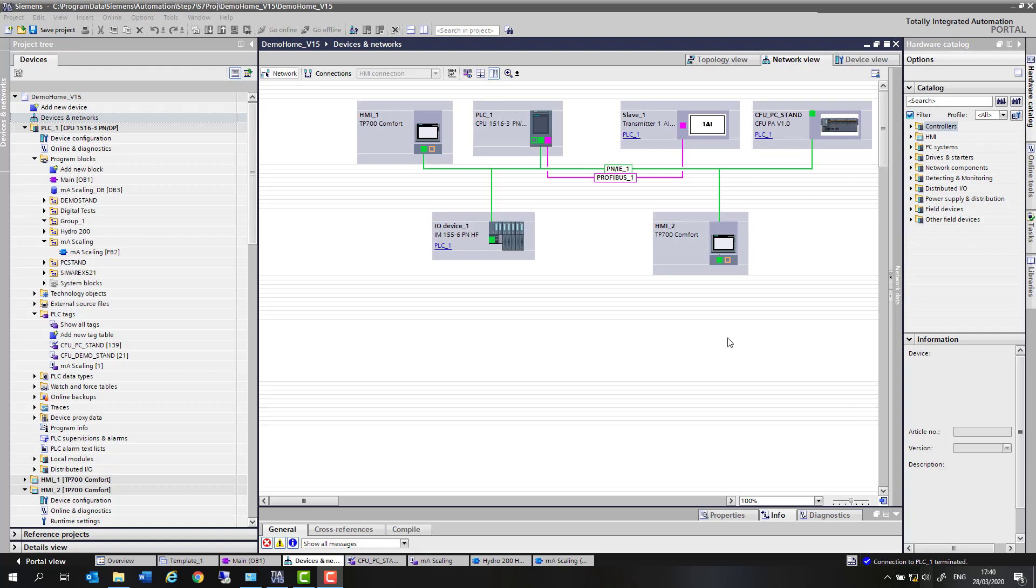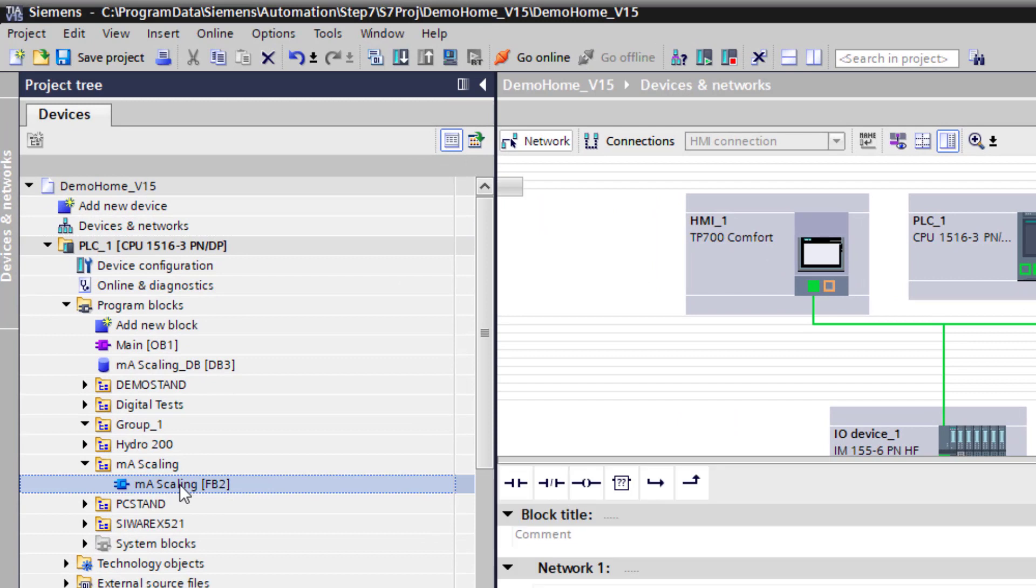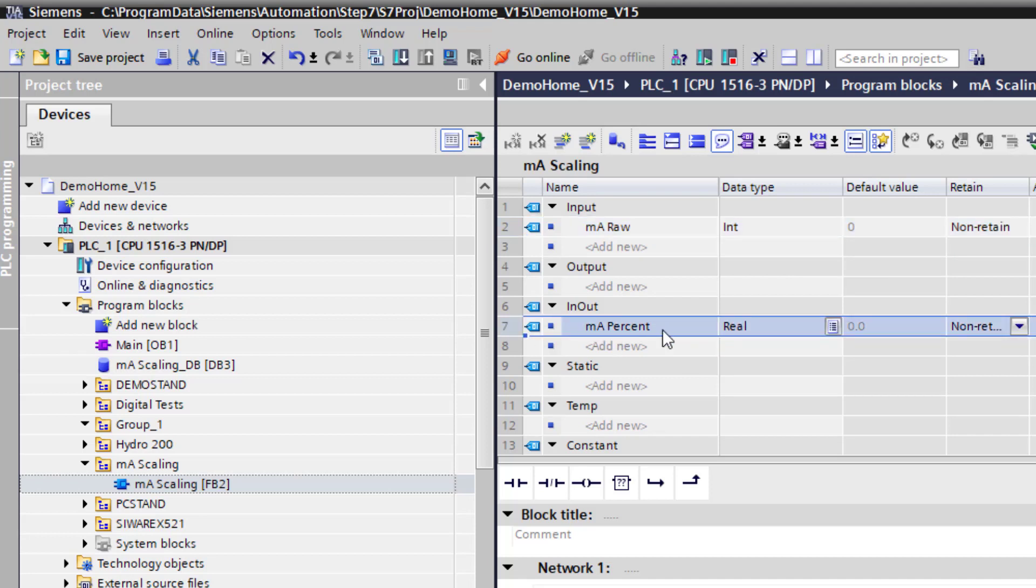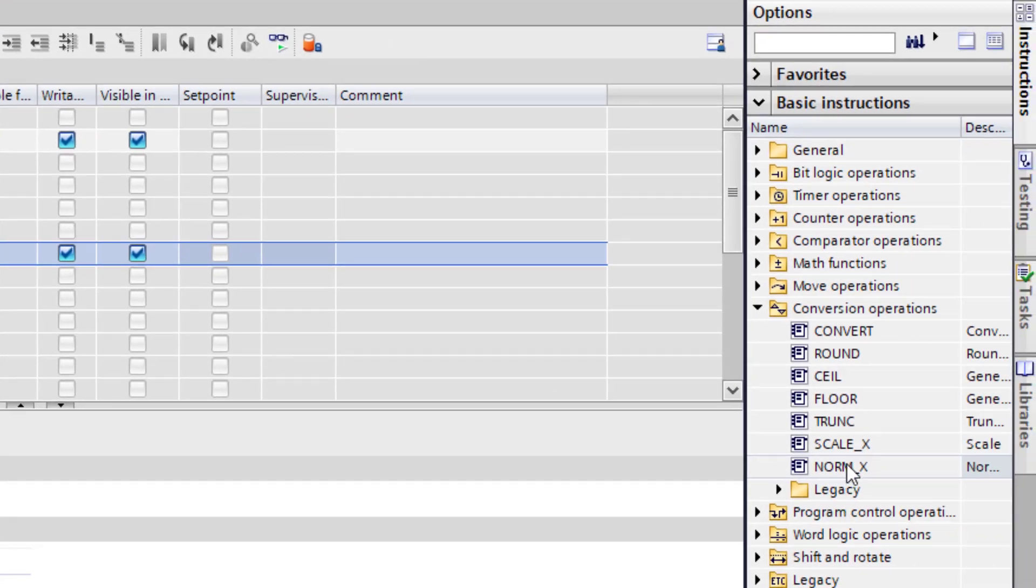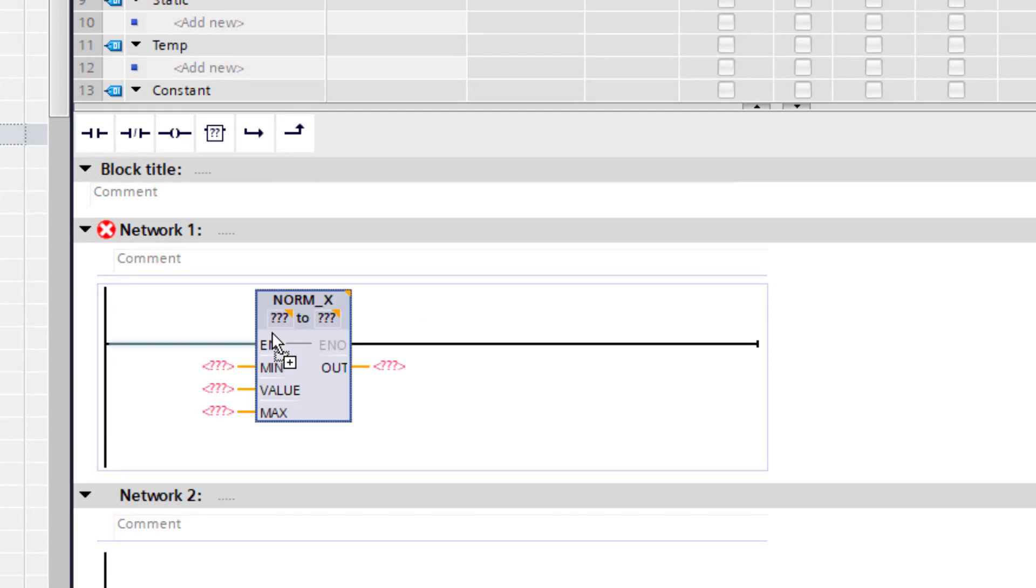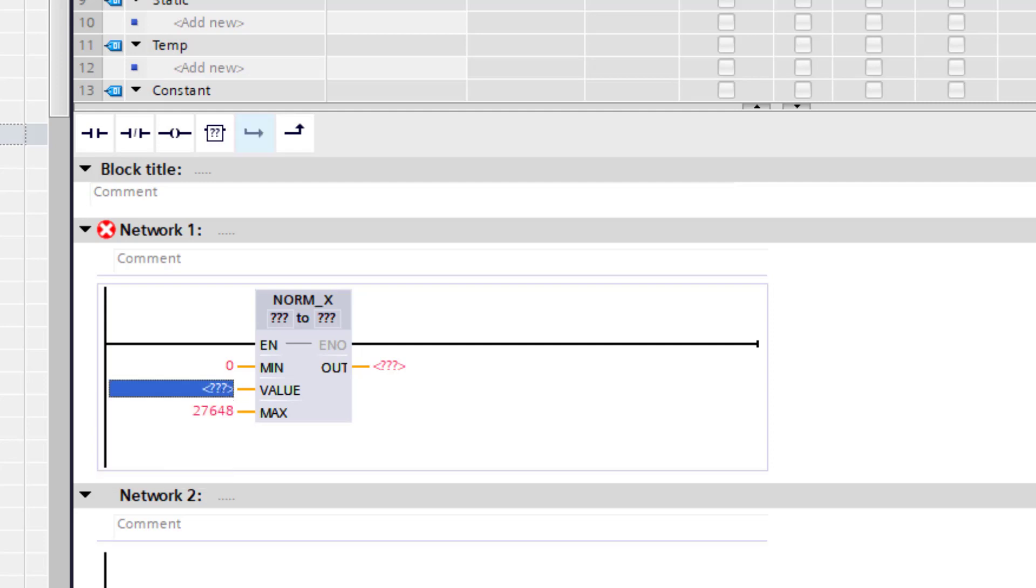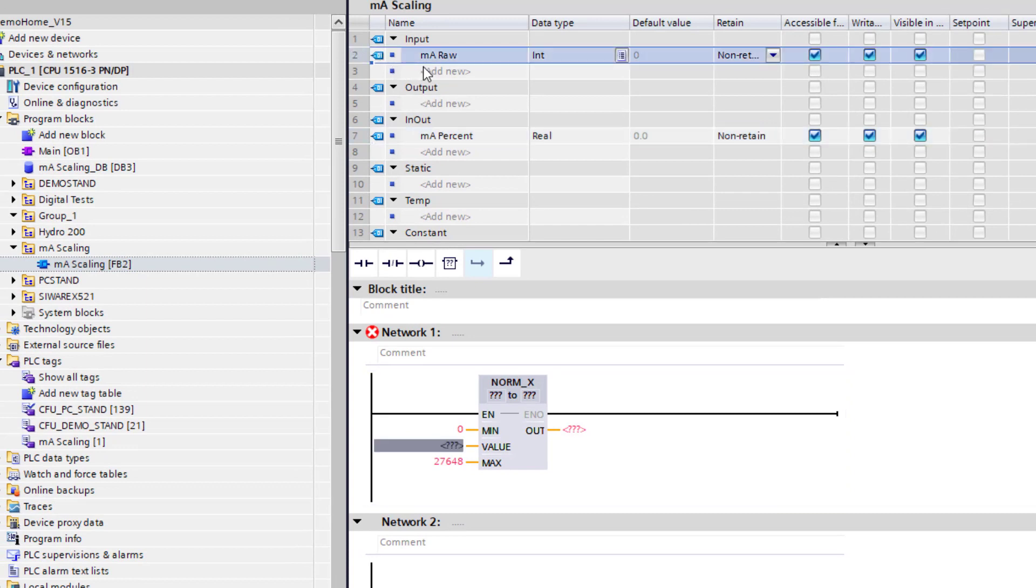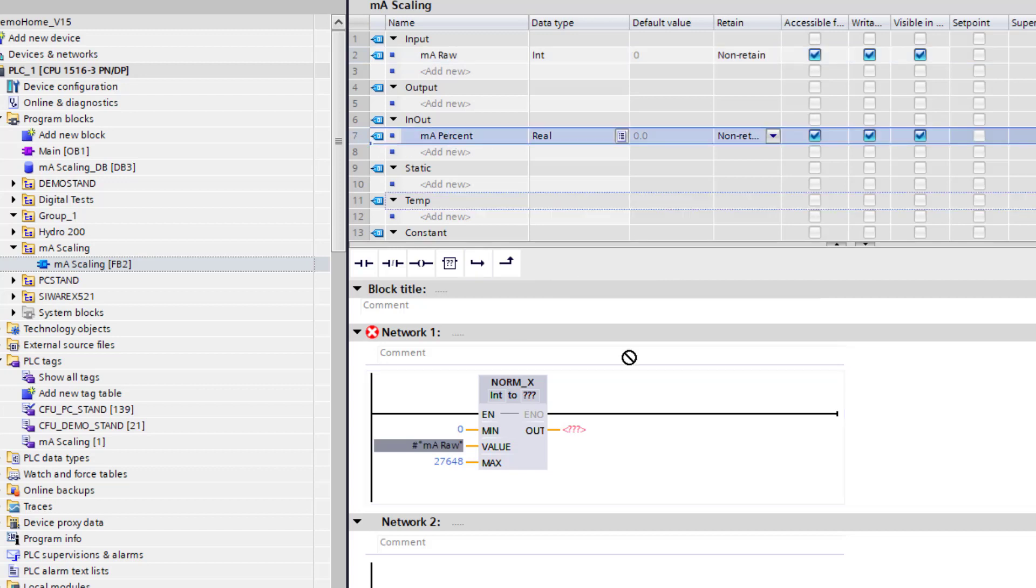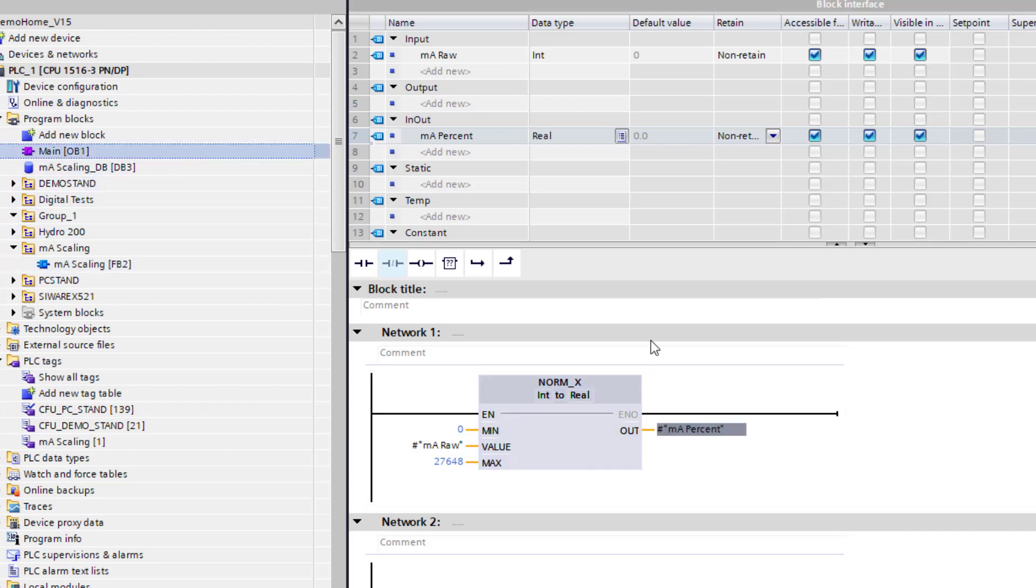So I've created a block called milliamp scaling, and within there I have a milliamp raw which is an integer. That's going to be linked to my input on the ET200SP card, and then the output from my normX function is going to be milliamp percent real. I've got that as an input-output because I need to link that to my scaleX block later on. So we'll put this normX block in, and then the scaling is 0 to 27,648. Because we're creating an FB function block, milliamp input raw here, and then the output in percent is going to be there. And I just need to put that into my OB1, which I've already done.